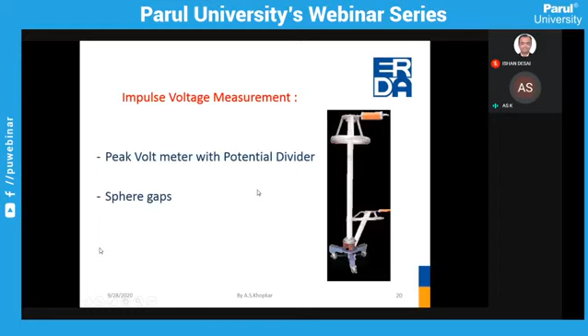This voltage divider we use for the voltage measurement in the laboratory. Sphere gap earlier days people were using, but it is time consuming and less accurate compared to peak voltmeter and potential transformer. So nowadays in the laboratory nobody uses the sphere gap measurement. If we wish to measure the impulse voltage, then again peak voltmeter with the potential divider and sphere gap. As I said, sphere gap can be used for measurement of impulse voltages also, but it is a time consuming process and less accurate, so people use peak voltmeter in the laboratory. So this was about the generation and measurement in the laboratory.